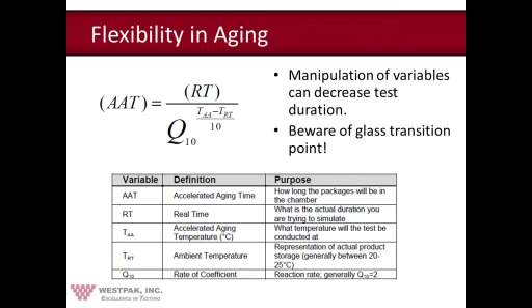If your protocol states an aging temperature of 50 degrees C, a 1-year shelf life would take around 56 days. However, increasing that aging temperature to 60 degrees C will decrease your aging duration by 28 days. And that's 28 days that you can add back onto getting your product out to market.